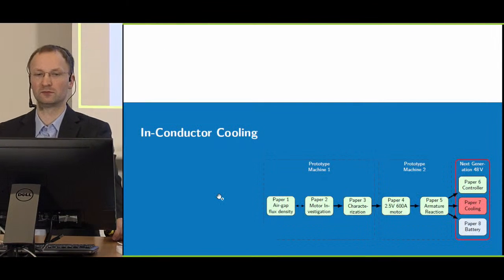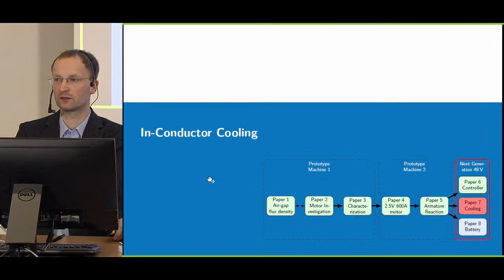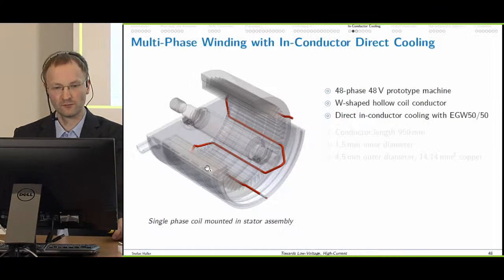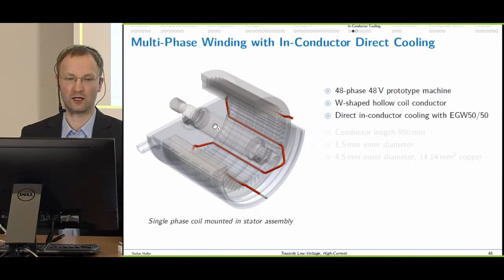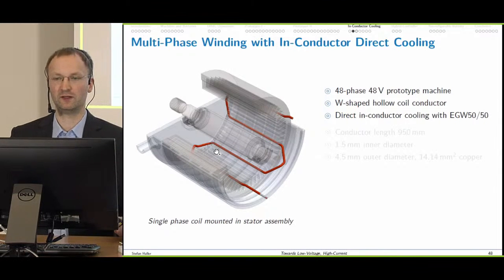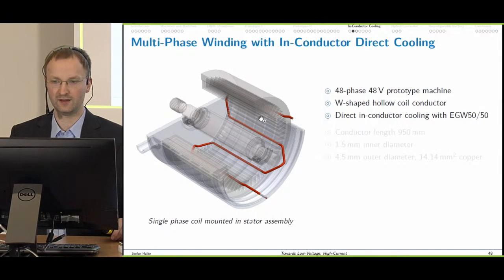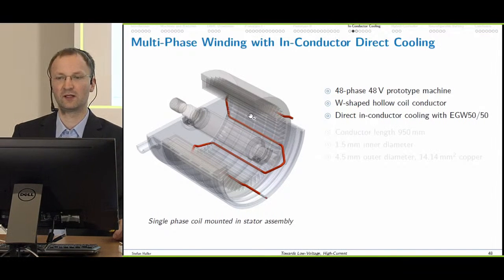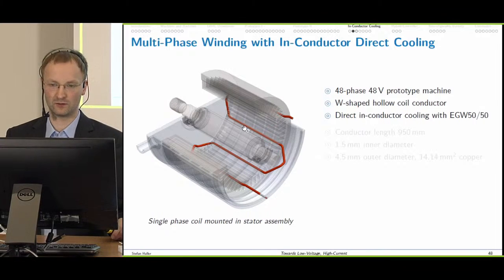Great. So let's have a look at in-conductor cooling now. This is a render of our current design stage of the 48-phase, 48-volt machine. What we see here is a W-shaped coil in red, one of the 48, that is hollow and designed for cooling with ethylene glycol water.